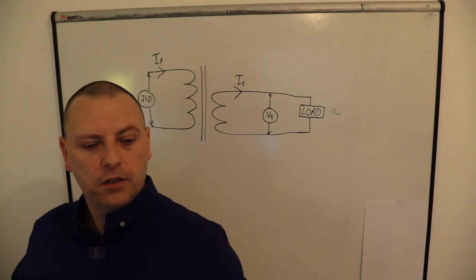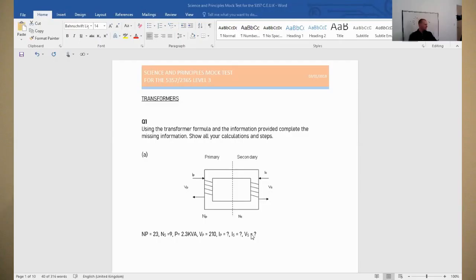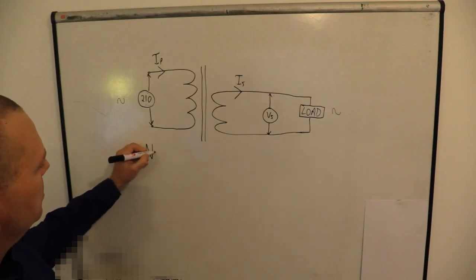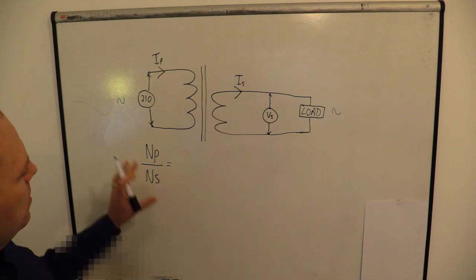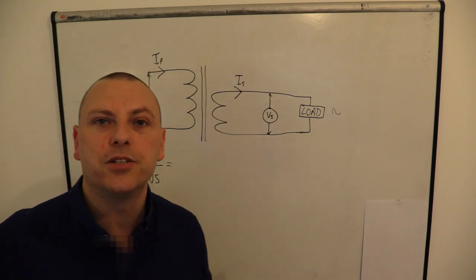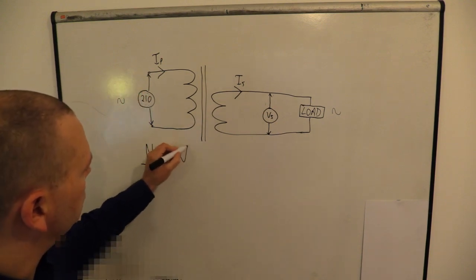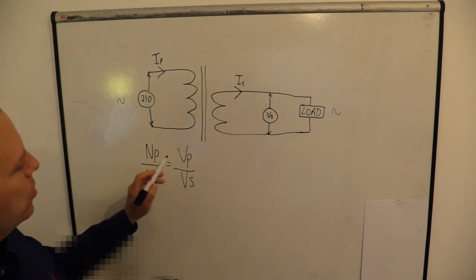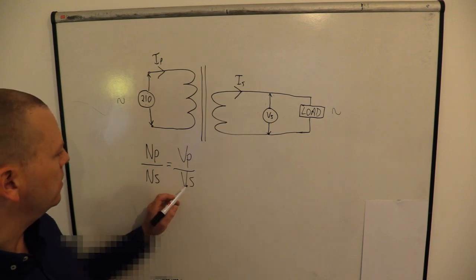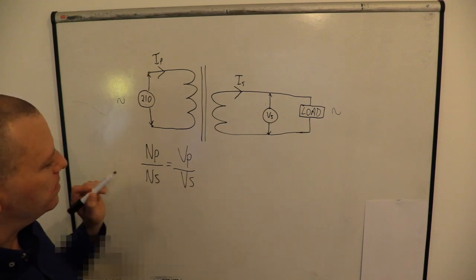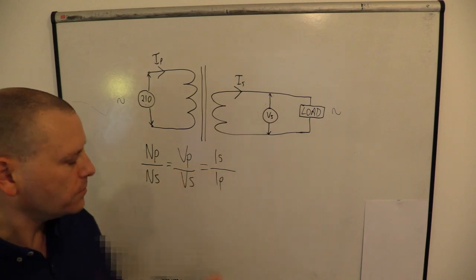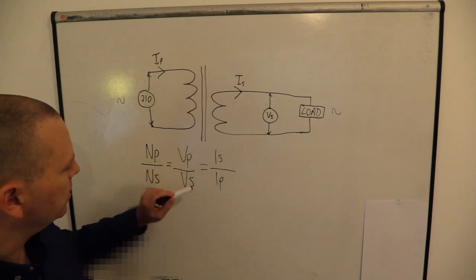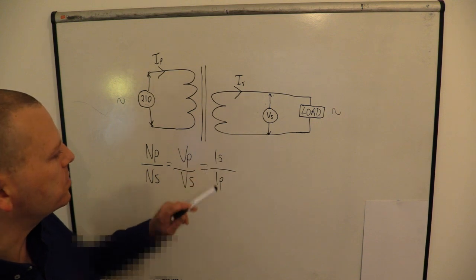We've got what we need to make a ratio - the primary turns and the secondary turns. So I'm going to start there and get that ratio. To get the ratio I'm going to use the transformer formula: primary voltage over secondary voltage equals primary turns over secondary turns, and that also equals secondary current divided by primary current. Note that we have primary over secondary, primary over secondary, and then for the current it's flipped - it's secondary over primary.